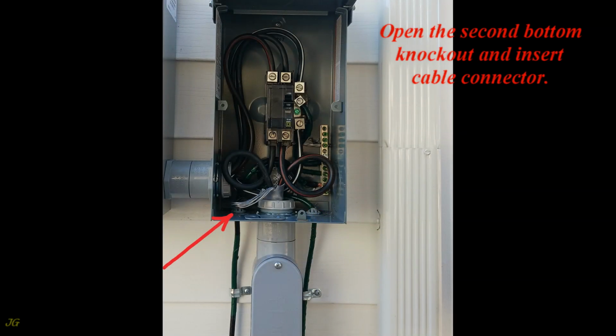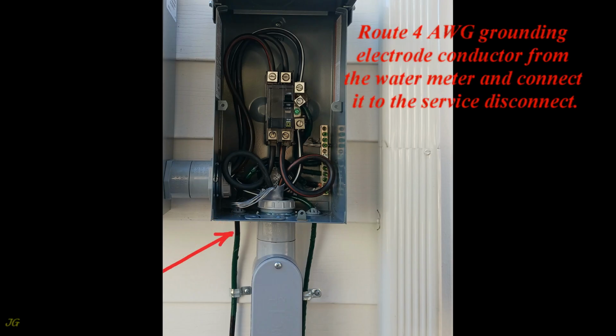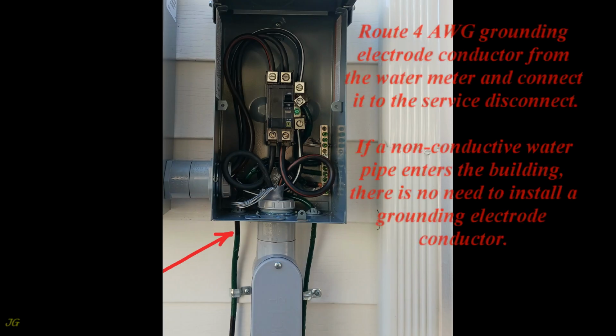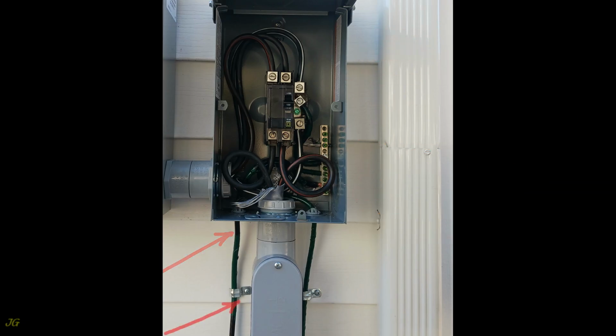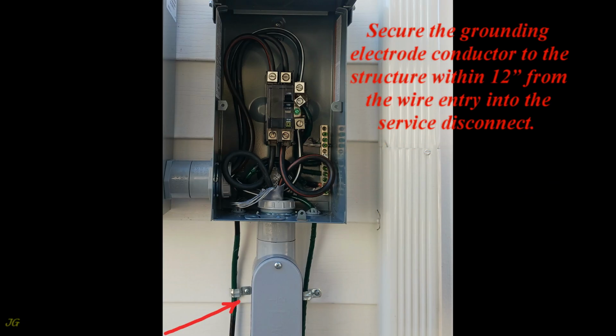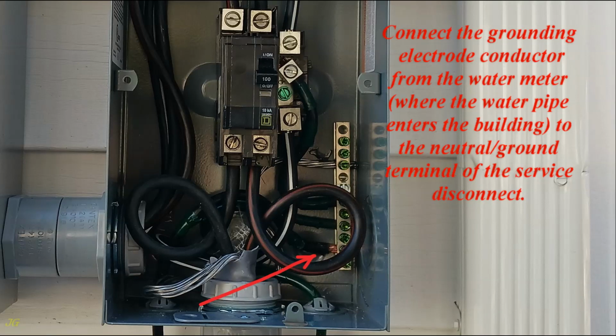Open the second bottom knockout and insert cable connector. Route 4 gauge grounding electrode conductor from the water meter and connect it to the service disconnect. If a non-conductive water pipe enters the building, there is no need to install a grounding electrode conductor. Secure the grounding electrode conductor to the structure within 12 inches from the wire entry into the service disconnect. Connect the grounding electrode conductor from the water meter, where the water pipe enters the building, to the neutral, ground terminal of the service disconnect.